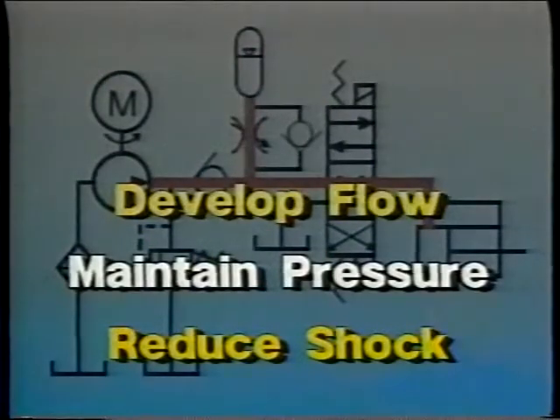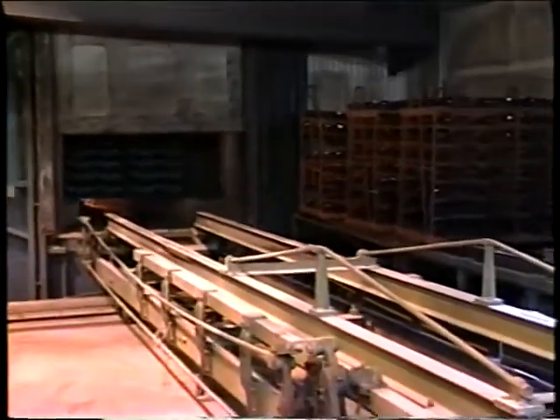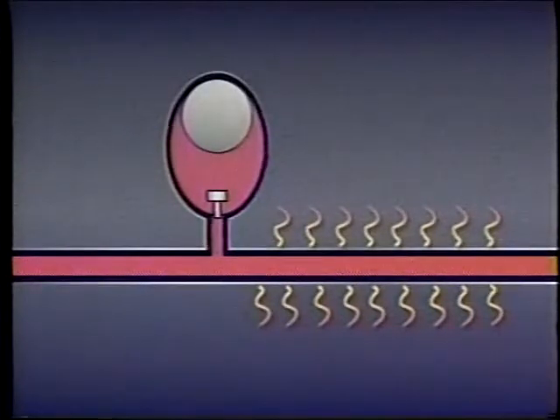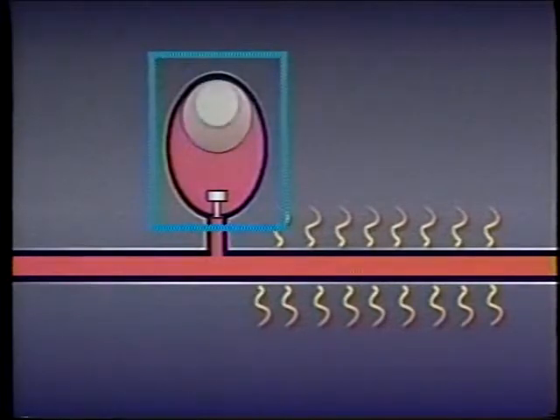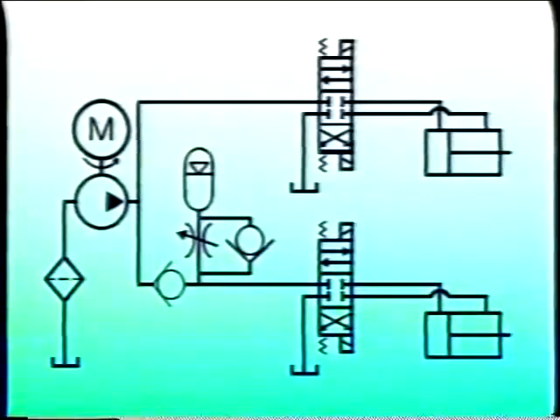Accumulators are also used to maintain pressure in hydraulic systems by compensating for both increases and decreases in pressure. For example, the fluid in a hydraulic system operating in a hot environment will expand and could increase pressure enough to damage components, fittings, or piping. However, a properly sized accumulator installed in the system will take up the extra fluid volume created when heat expands the fluid, so pressure will remain relatively constant.